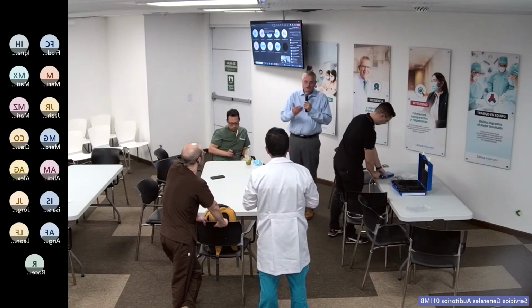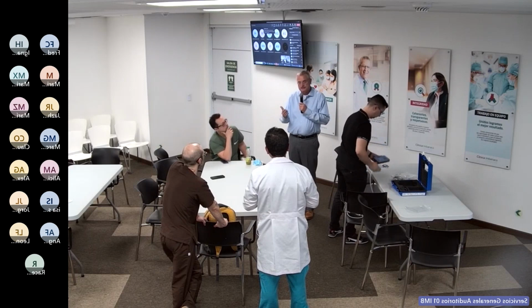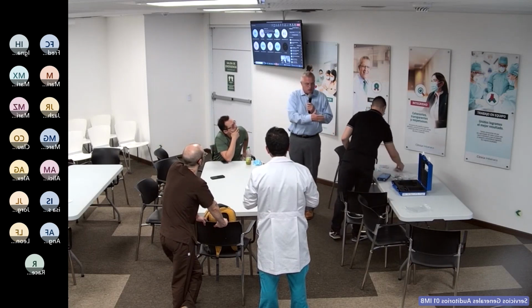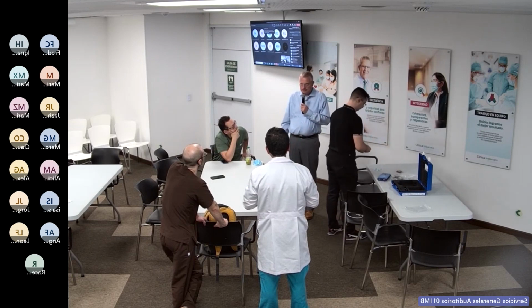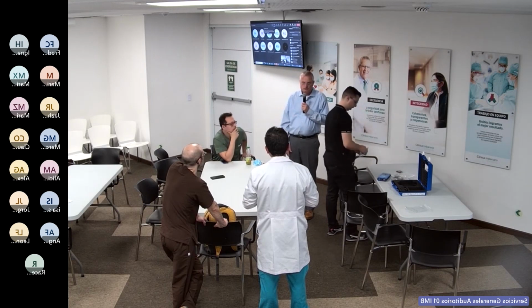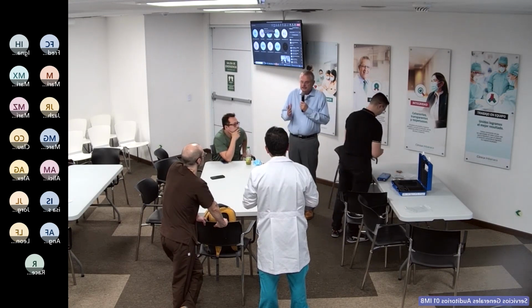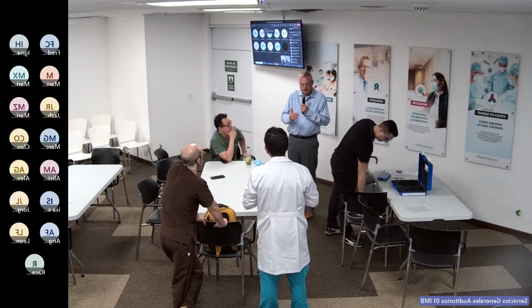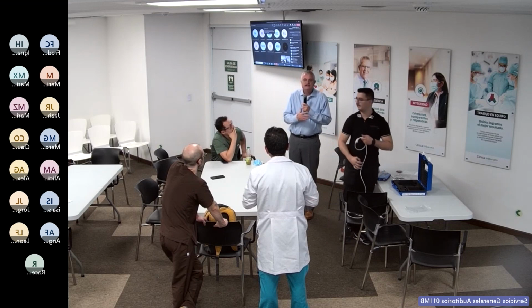Well, actually, that's what we thought too, that, for example, sickle cell disease would make this cardiac output measurement less accurate. But we haven't done a study, but we have come across approximately 2 or 3 patients, and they showed a very good match with thermodilution. So can I say it works on every sickle cell patient with the same accuracy? No. But so far, we haven't seen any indication that sickle cell disease actually increases the inaccuracy of the system.